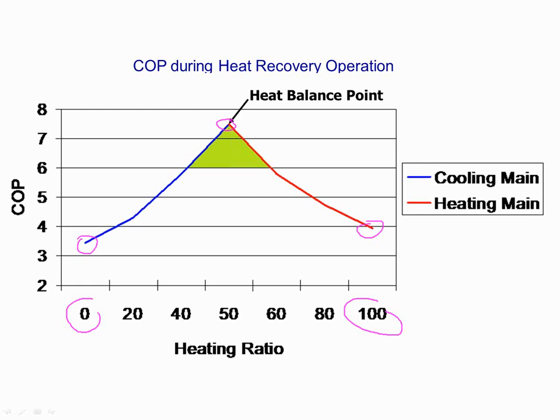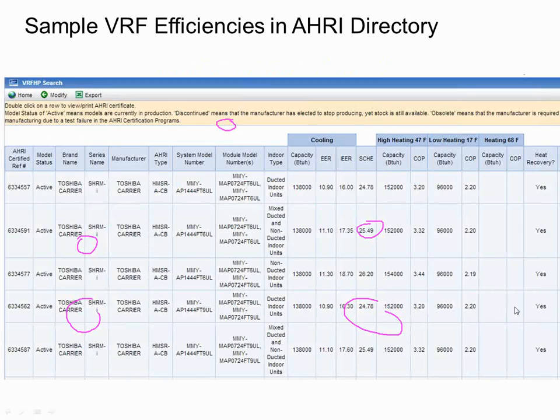Well, with VRF, we do quite the opposite. When we start doing these VRF systems, and specifically heat recovery VRF systems, we start telling people, the more zones I have calling for the opposite mode at the same exact time on the same unit, the more efficient I get. So please take some of your interior zones and mix them with your south exposure zones. Please go ahead and mix the east and west guys together because they probably need opposite things at certain points of the year. So it does get a little bit interesting in terms of how we lay a building out compared to other DX systems. I really do want to mix the exposures, unlike a traditional system, to get more simultaneous heating and cooling hours.